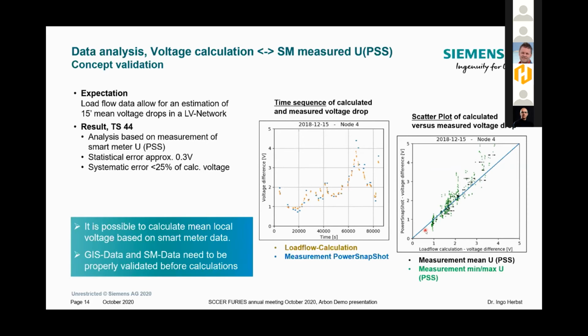So what we think is that GIS data and smart meter data, once debugged and validated and properly taken, will give you reasonable voltages when doing the calculation. The systematic error is maybe 25%, and the statistical error just from the digitalization of the smart meters is around 0.3 volts.